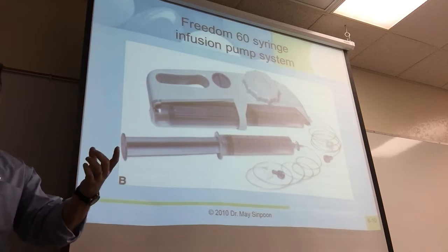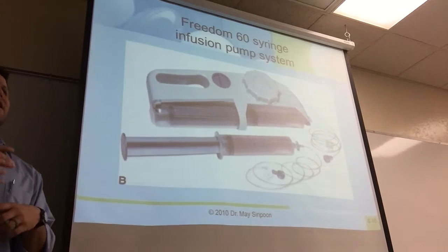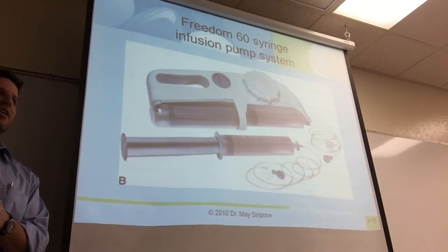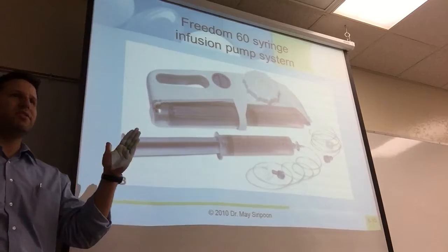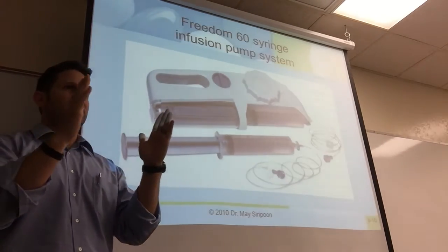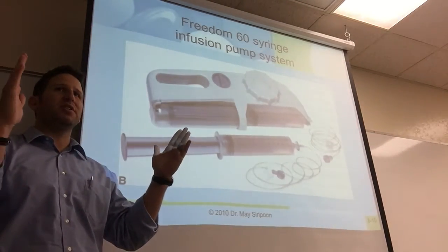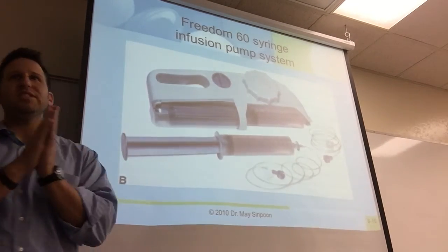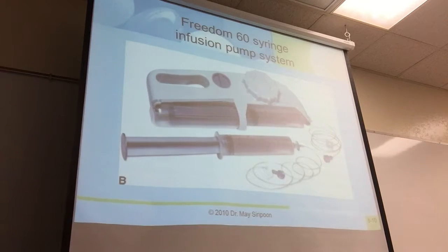If I'm using one that's not in its database, then I can select other, and then it will take the measurements while you pull it out and clamp it in. You put, this is a 12cc syringe. Then if it knows that for 12 cc's, this has to go over so many centimeters, then it has that measurement, and it will decrease its size and slowly compress to infuse at the right rate. That's very awesome. So pretty cool. Stuff you wish you invented. It's the most exact way to give medications to the pediatric patient. Even for those critical patients on drips, they'll put it in the syringe pump, and that's actually more effective than putting them in the big IV pump.